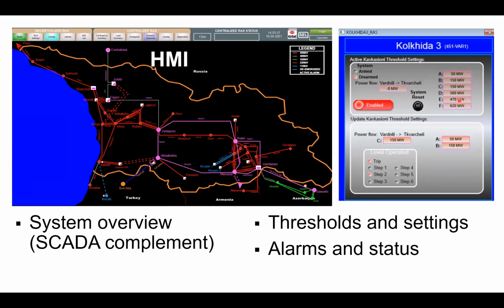So this is a full HMI with the full capabilities, such as we have in a SCADA system, for instance, but only designed for ECS purposes. So it is not connected to the SCADA HMI system. It is a separate and standalone system. The operator in a GSE National Control Center monitors both systems at the same time, SCADA HMI and ECS HMI. This is what I wanted to say.